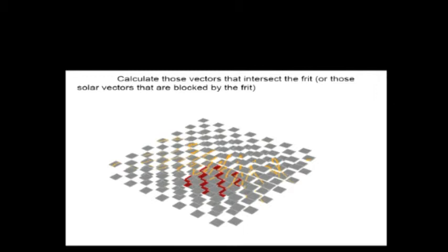And we made a simple assumption here that when you have cooling load in the space, then when you add up the direct beam associated with the solar vectors that are imposed on the frit pattern and aggregate them, the kilowatt hours per square meter you get out of that is the savings, or that's how much heat you're actually avoiding in the space.